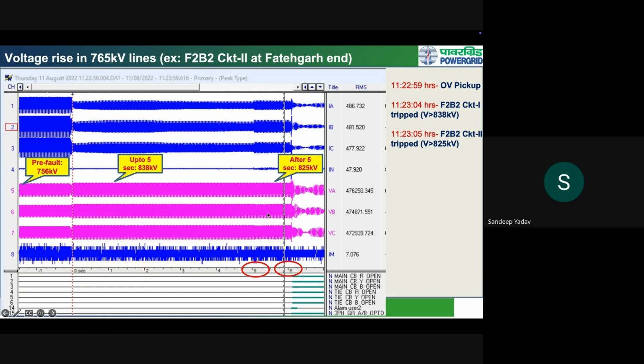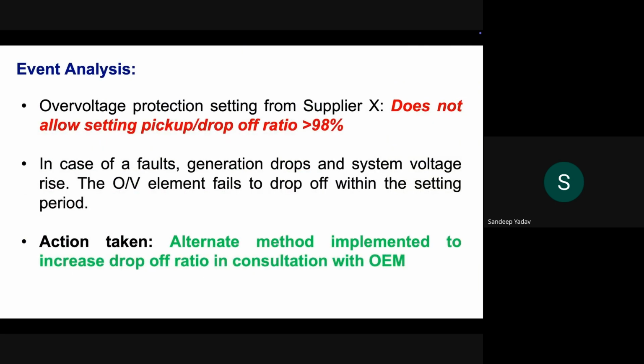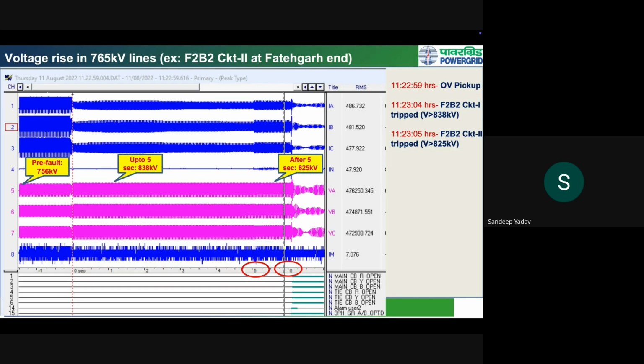So this is the problem if the generators do not meet the grid code. For example, if the active power comes back to 90% of the pre-fault power within 1 second, the lines will be loaded again, and the voltage will fall to somewhere close to the pre-fault voltage, and these trippings on over voltage would not happen.